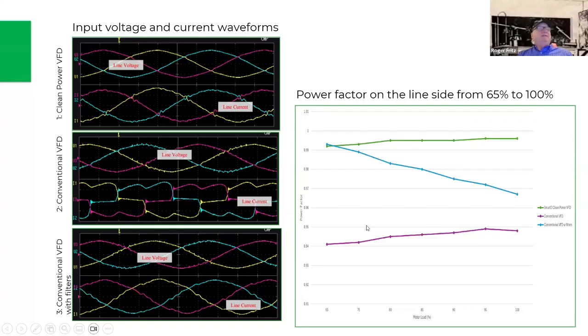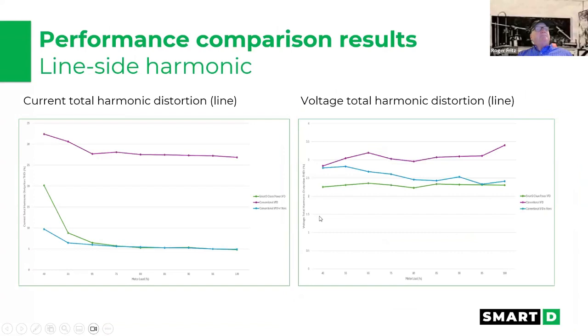A lot of them play around with displacement power factor and real power factor, but at the end of the day, the power companies have become very much aware of this, and you'll see that on your power bill, that the total kVA demand of the buildings is going up and up. This is an idea of where the line distortions are happening in the marketplace. You'll see that the conventional VFD noise is up here as high as 35 to 40%. And the actual IEEE 519 is supposed to be less than 5%.